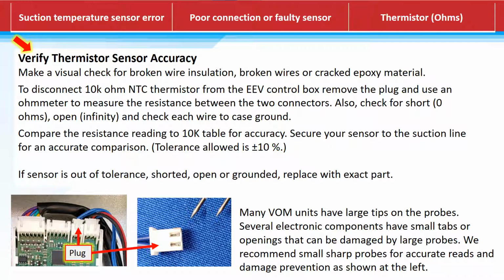Make a visual check for broken wire insulation, broken wires, or cracked epoxy material. To disconnect the 10K sensor from the EEV control box, remove the plug and use an ohm meter to measure the resistance between two conductors. Also check for a short, which is 0 ohms, open, infinity, or check each wire to case ground. Compare the resistance reading to a 10K table for accuracy. Secure your sensor to the suction line for an accurate comparison. There's an allowed tolerance of plus or minus 10% on this read. If the sensor is out of tolerance, shorted, open, or grounded, replace with the exact part.